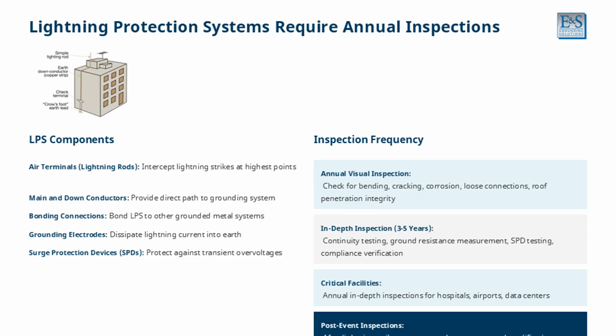Lightning protection systems require annual inspections and periodic in-depth testing. These systems consist of 5 key components: air terminals or lightning rods that intercept strikes at the highest points, main and down conductors providing a direct path to the grounding system, bonding connections that bond the LPS to other grounded metal systems, grounding electrodes that dissipate lightning current into earth, and surge protection devices that protect against transient overvoltages.